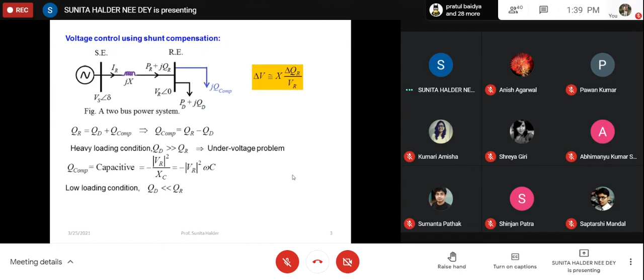These shunt compensating devices are also called local VAR generators. Why local VAR generators? Because you are connecting at the load end, so the load side will decide whether to connect or not. Sending end is not controlling that; the receiving end substation will decide whether to connect the shunt capacitor or shunt compensation or not.